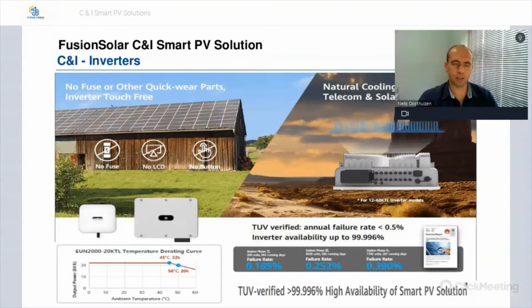So moving over to the next slide on the Huawei C&I inverters. Huawei has taken a thorough approach to the system. Because the inverters have a 25-year warranty, it's a really long lifetime that they guarantee. So in their research, when they first approached this market, they identified certain components as high failure components. And with their design, they've actually taken those components out to ensure that the inverter can last its full lifespan of about 25 years.